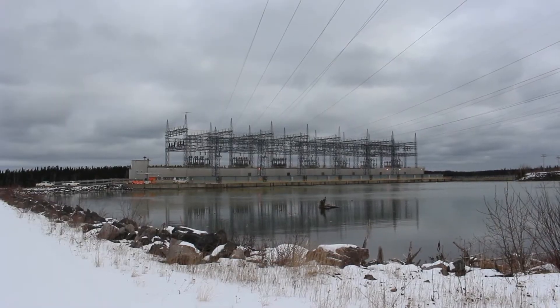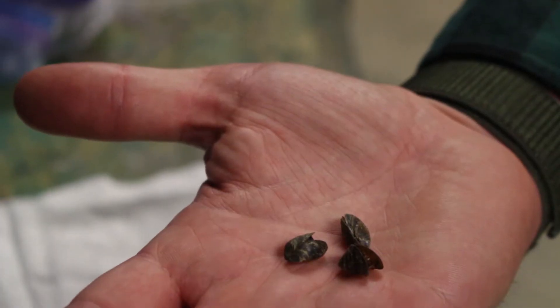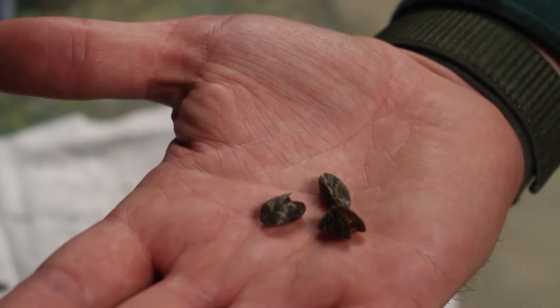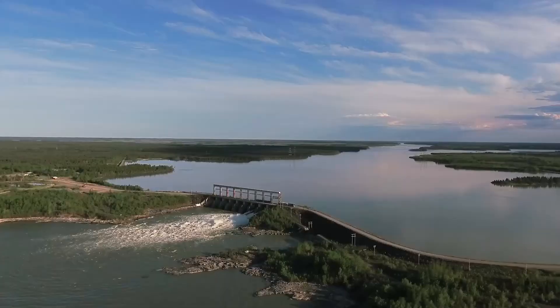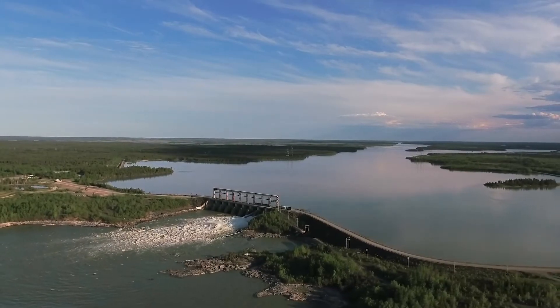Our plan is to use chlorine to inject our systems. The mussels will intake that chlorine and it will kill them off. We're using residual amounts of chlorine — 0.6 parts per million — similar to the chlorine you'd find in your drinking water. Once this chlorine and water is flushed through our raw water lines, we then neutralize it before releasing it to the Nelson River.